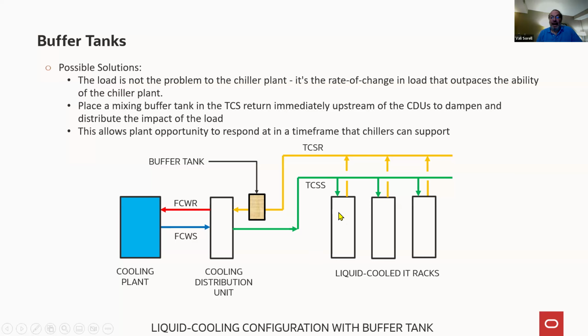So let's go back to that hypothetical, not so hypothetical, actually a real situation that we have seen does occur. The racks or the GPUs do ramp up. They put a slug of hot water, and the buffer tank, being a mixing tank, instead of immediately going up to the return temperature that would hit the CDU, which then gets transferred to the chiller plant, mixes it. So all it does is dampen it. This buffer tank, all it needs to do is hold the water, mix it. So instead of having a sharp spike in the temperature of the return water, it mixes, blends. There is a spike, it does increase, but the important thing is not to eliminate that rise in temperature.